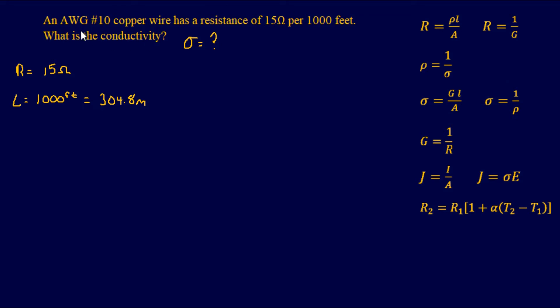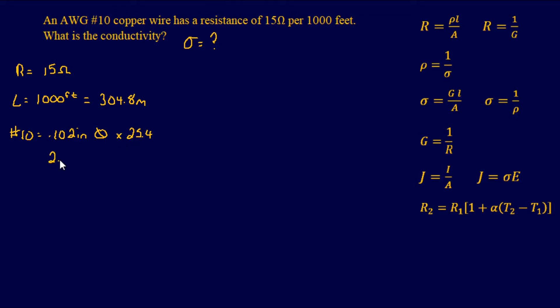Now to find the area, we have to look up in our code book what a 10-gauge wire diameter is. The 10-gauge wire in our code book is listed as 0.102 inches in diameter.